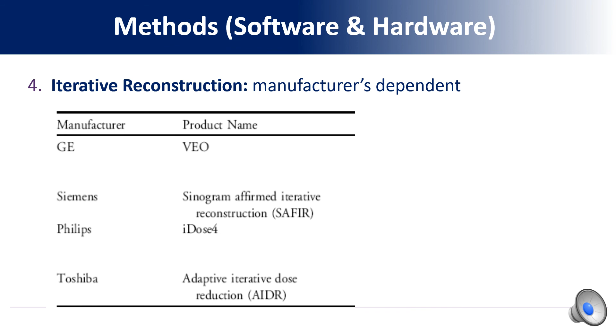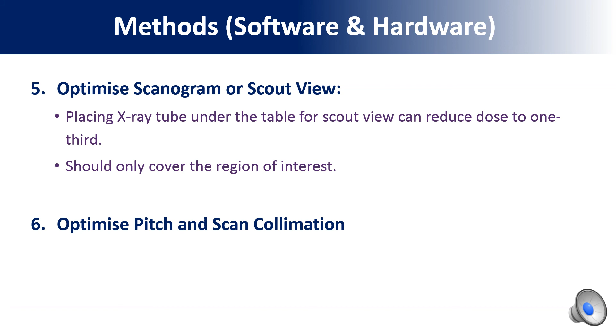And finally, we can optimize the scanogram or scout view. By placing the X-ray tube under the table for the scout view, we can reduce dose to one-third. And the scout view should only cover the region of interest. And lastly, we can also optimize the pitch and scan collimation. Optimal collimation is very important in dose reduction and avoids unnecessary radiation to other parts of the body.